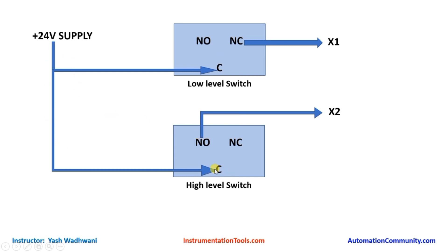Similarly, for the high level switch, we give 24V supply to the common and connect the NO terminal to X2 of the PLC. When the high level switch floats upward, the common and NO terminals are closed, so power flows to X2, signaling the PLC that the water level is high. This is the working of the level switches.